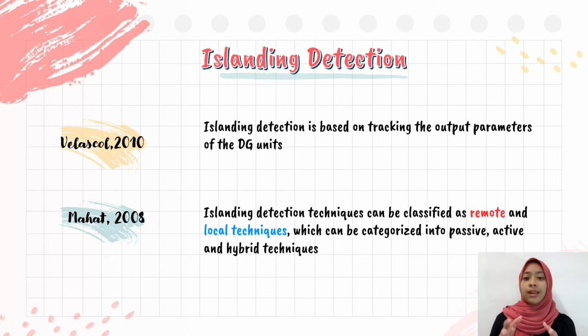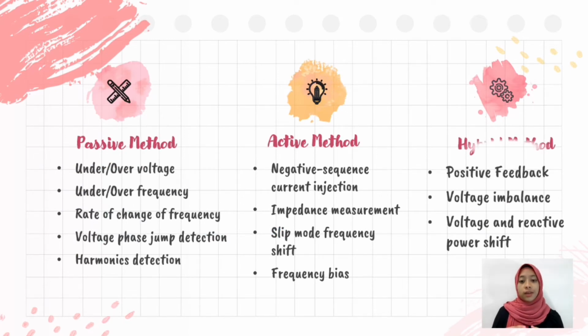Velasco states that islanding detection is based on checking the output parameters of DG units. But Mahat states that islanding detection techniques can be classified into remote and local, and local can be categorized into passive, active, and hybrid. These are the techniques for each method. First, the passive method: under or over voltage, under or over frequency, rate of change of frequency, voltage phase jump detection, and harmonic detection. Second, the active method: negative sequence current injection, impedance measurement, slip mode frequency shift, and frequency bias. Lastly, the hybrid method. There are three: positive feedback technique, voltage imbalance technique, and voltage and reactive power shift technique.